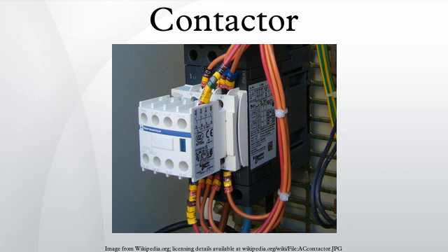Applications: lighting control. Contactors are often used to provide central control of large lighting installations, such as an office building or retail building. To reduce power consumption in the contactor coils, latching contactors are used, which have 2 operating coils. One coil, momentarily energized, closes the power circuit contacts, which are then mechanically held closed. The second coil opens the contacts.